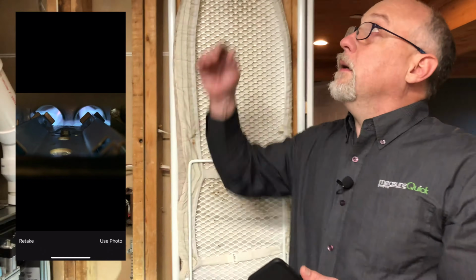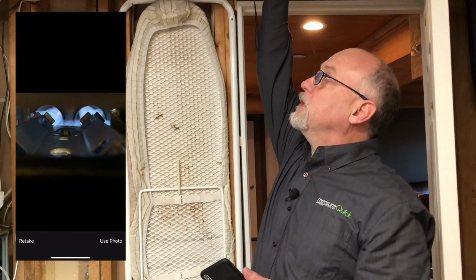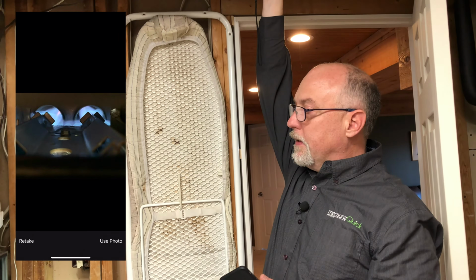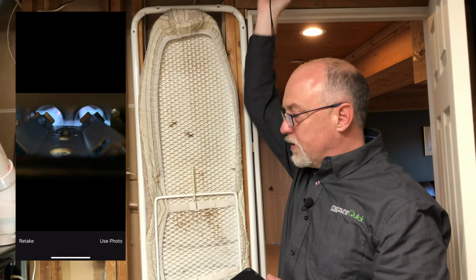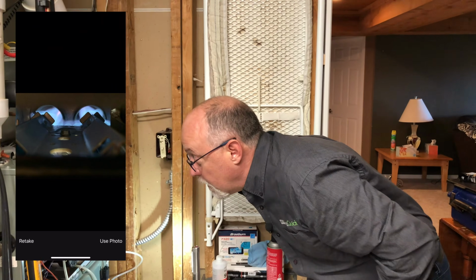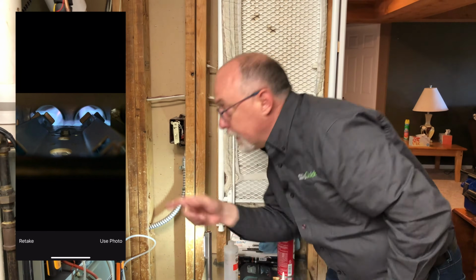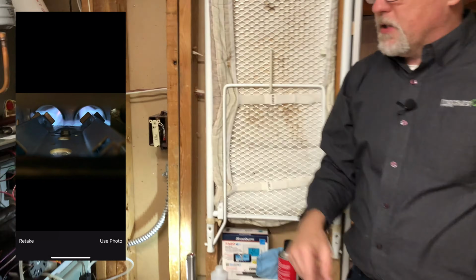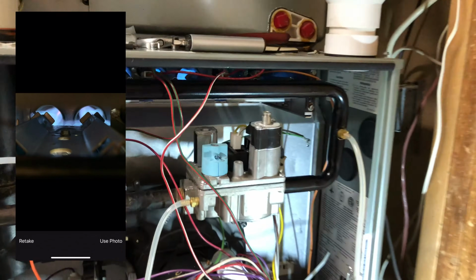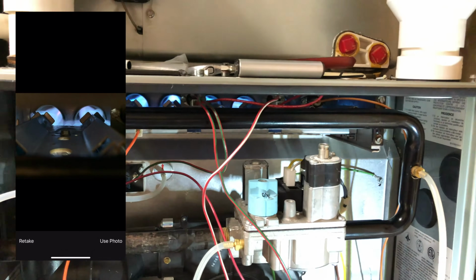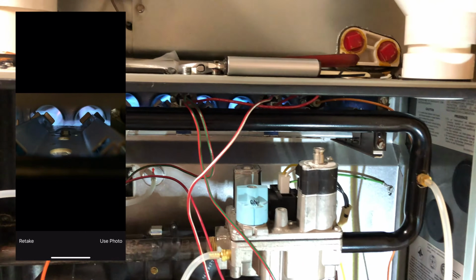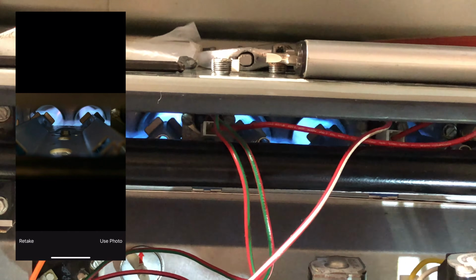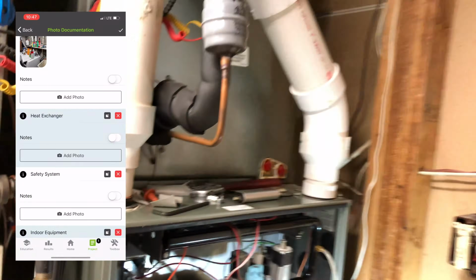As soon as that blower starts, which I believe is starting, it hasn't quite started yet, we'll let it get to a warm up here, and there it's starting just now. ECMs are hard to hear. Then go ahead and look in here. You can take a look at the camera, and you can see the flame in there looks really nice and smooth. Go ahead and get in there a little closer if you can, so you can get a good look at that. What we're looking for again is flame disruption, and in this case that looks really good on the appliance. So we'll use that photo.